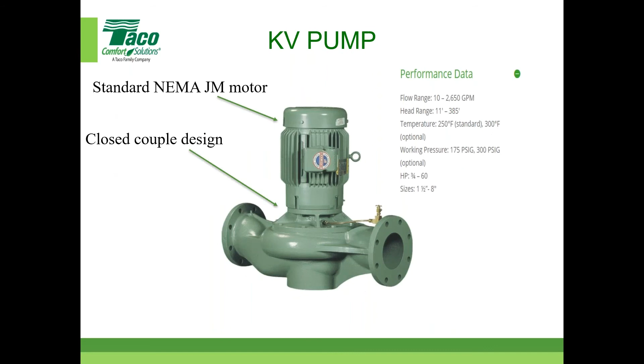So that's some of the general information on the KS pump. Here's the KV pump, a little different, right? Closed couple design. You can tell the difference. You don't see that little stand, the support stand with the coupler. In this case, the motor is bolted right to the impeller and to the top of the casing as well. That's what we call a closed couple design in HVAC hydronic pumps, and it's a standard NEMA JM motor used here.